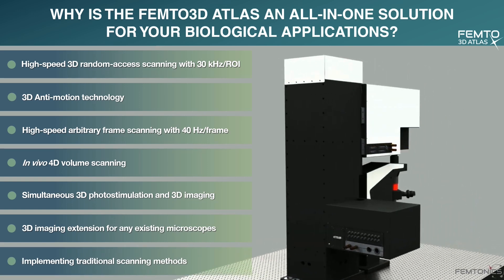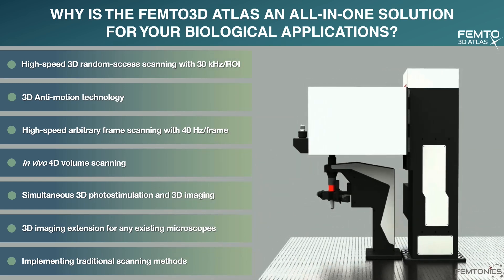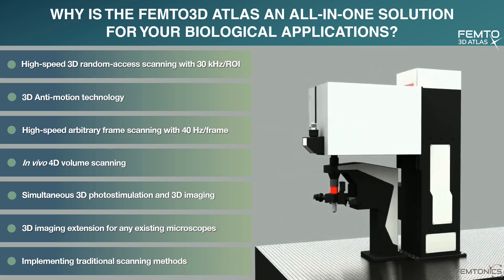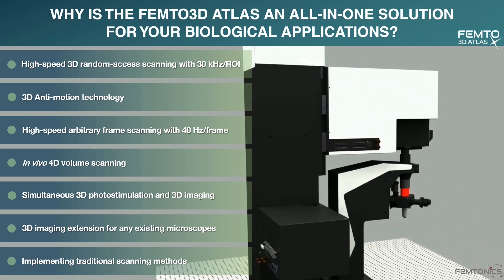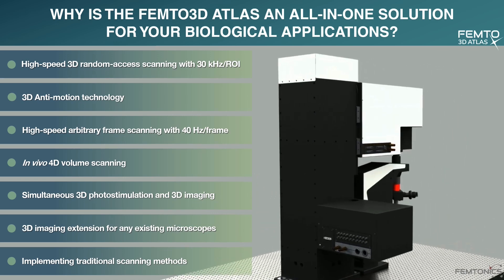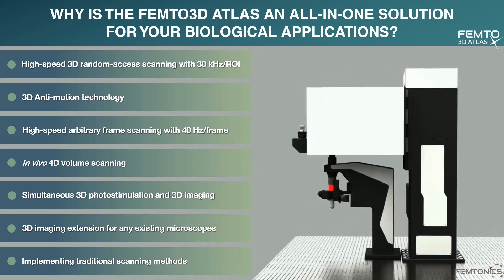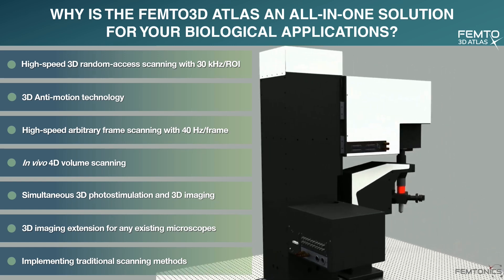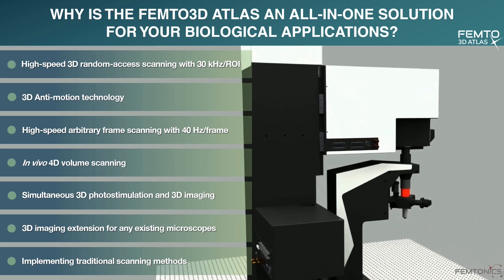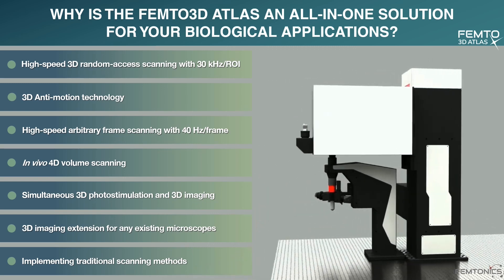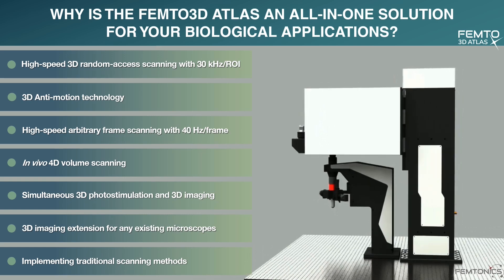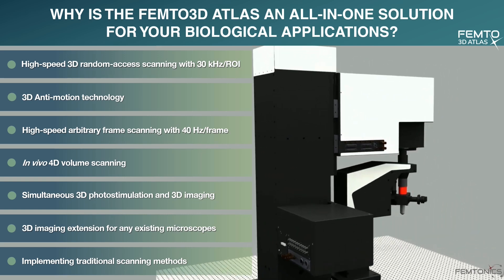With high-speed 3D random access scanning, an astonishing 30 kHz speed can be reached at your region of interest. The 3D anti-motion technology eliminates artifacts arising from the movement of the sample, making the system suitable for the imaging of behaving animals. High-speed arbitrary frame scanning provides 40 Hz per frame scanning speed. Thanks to the acousto-optical technology, the imaged plane can be arbitrarily chosen, tilted, and rotated. In vivo 4D volume scanning allows imaging along the entire length of different cells in different layers for extended periods of time. Using two laser lines, biologically simultaneous 3D photo stimulation and 3D imaging are possible. You can also choose to upgrade your existing upright microscope with this outstanding 3D technology. With Femto3D Atlas, you will have access to the benefits of conventional 2P microscopy and ultra-fast 3D imaging.